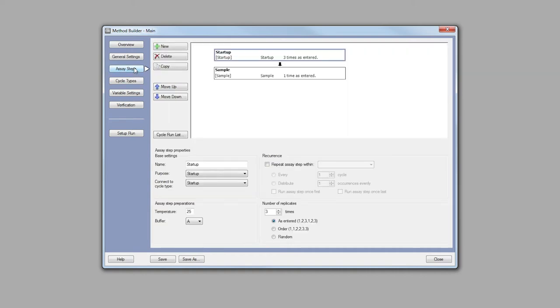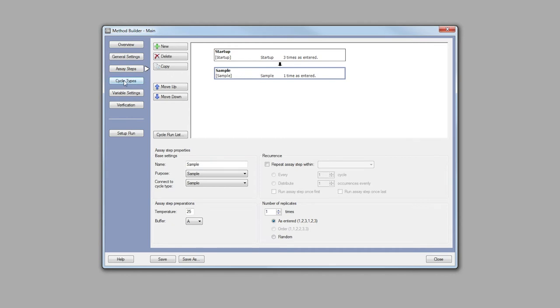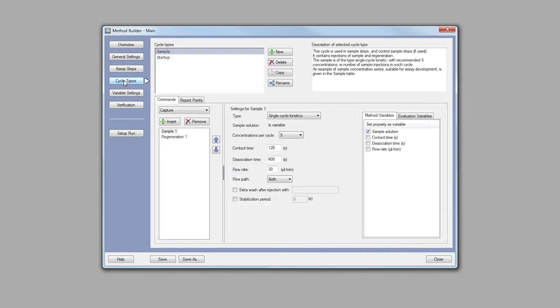Next, select assay steps, where the number of replicates and temperature can be selected. Cycle types describes the sequence of commands within an assay step. In this single cycle experiment, the cycle types include a sample and a start-up cycle type.